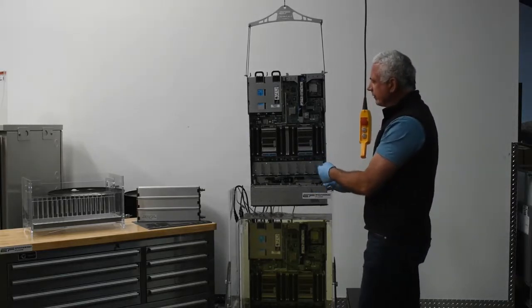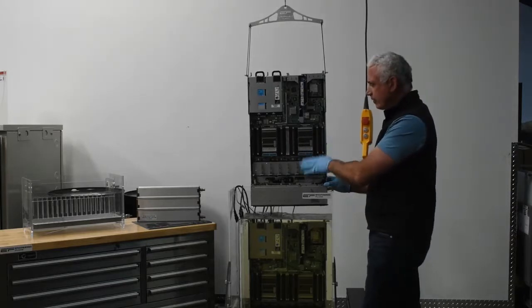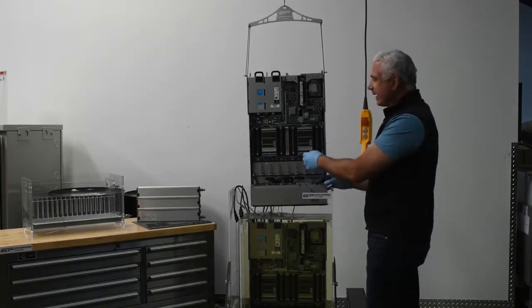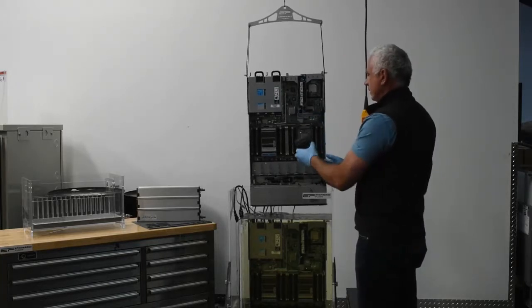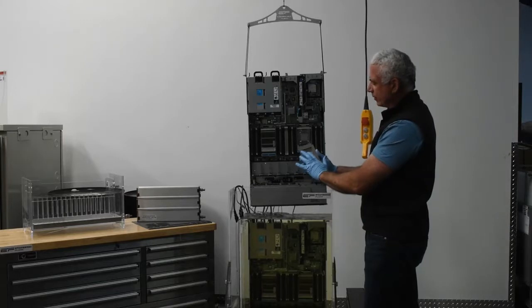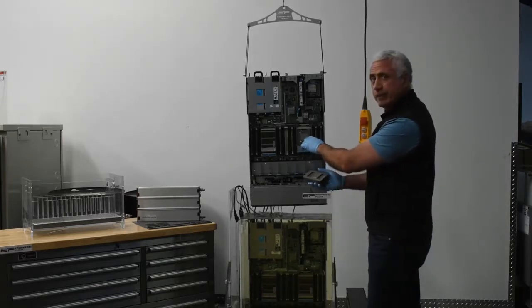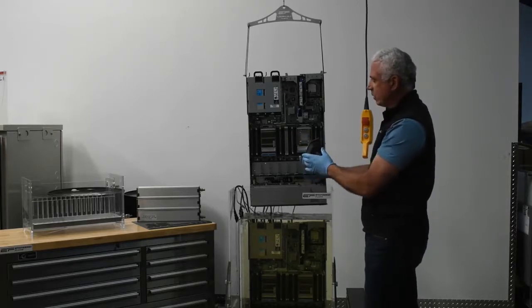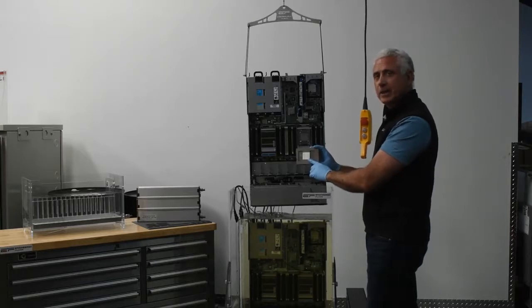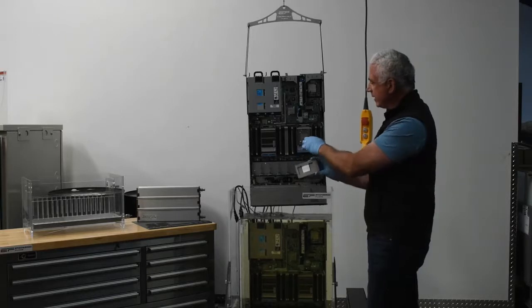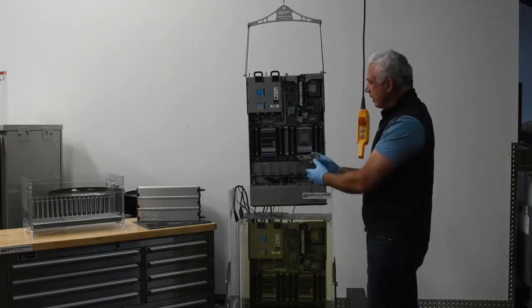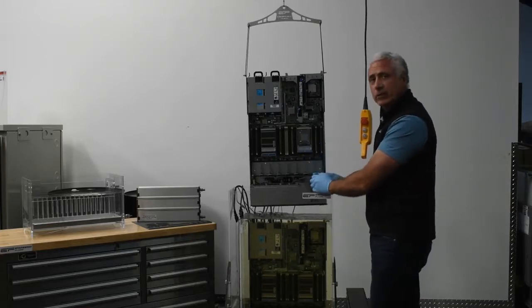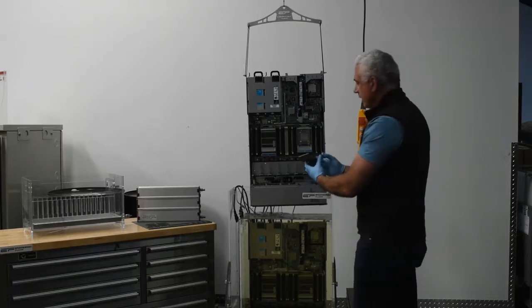So one of the things I want to show you is one of the things that we did to prep this server prior to immersion is to actually fix and clean the thermal grease that is typically placed on the back of this heat spreader. There's our CPU. You can see how easy it was to remove the heat spreader. And what we've done is we've placed a small piece of indium here on the back of this. We do this because it helps to spread the heat from the processor to the heat spreader. Once you've done that we've cleaned off the thermal grease that was here originally. We do that to prevent contamination.